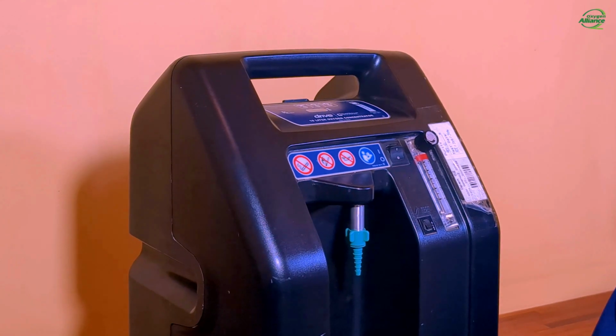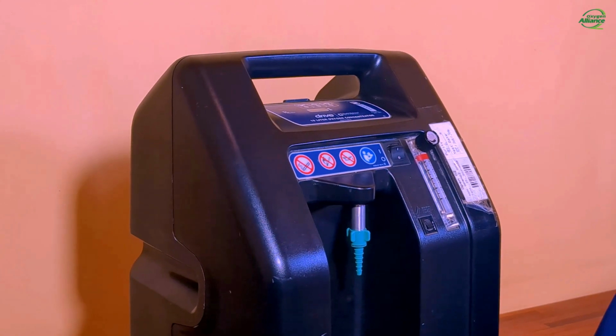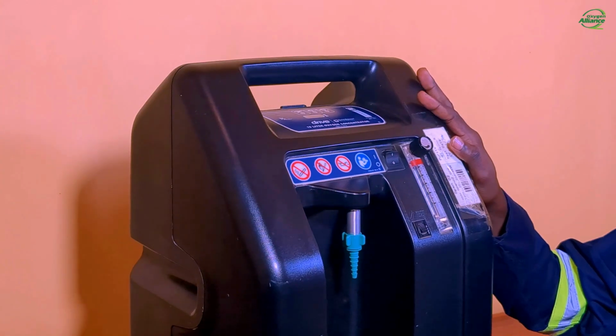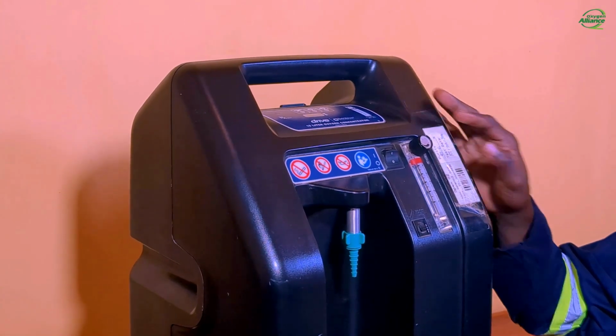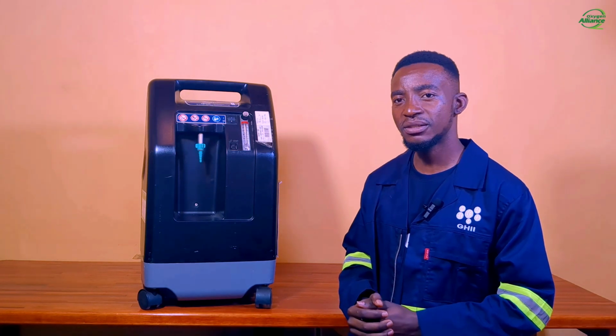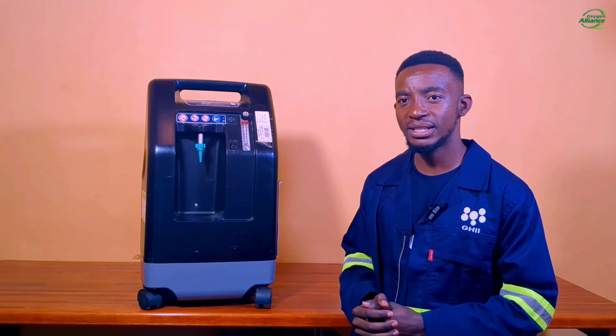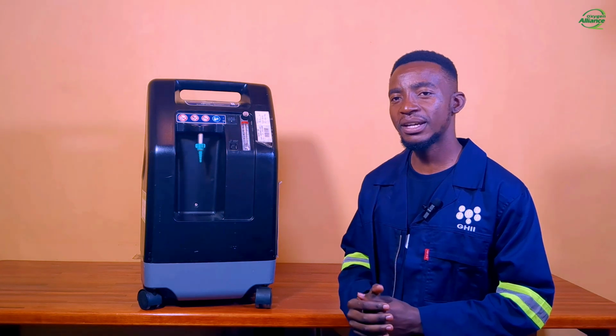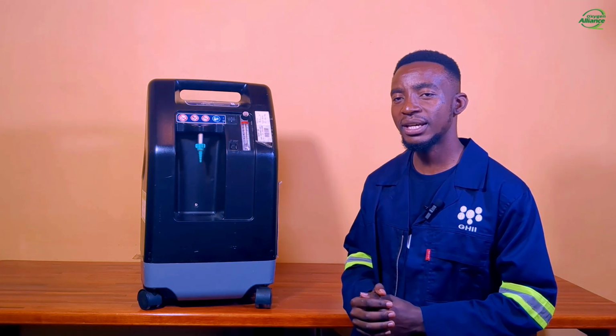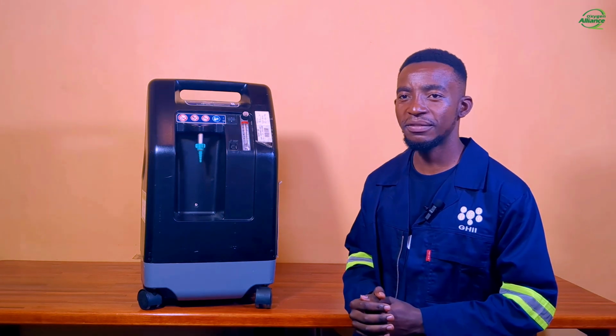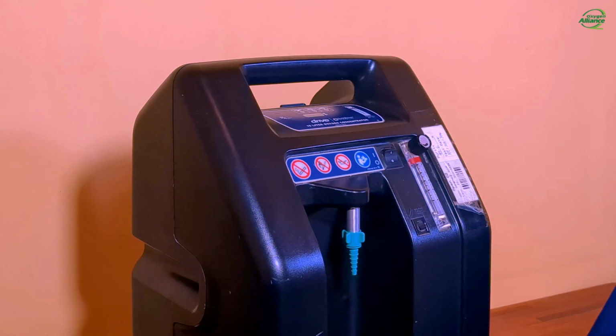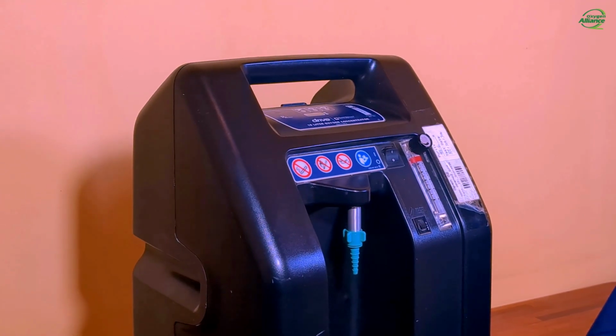The DeVilbiss 1025 Oxygen Concentrator has a maximum capacity of 10 liters per minute, and it delivers oxygen with a concentration from 87 to 95.6%. So this model, there are three variants of this model, the difference being the voltage rating. We have the 1025 DS, which is 110 volts AC, and we have the 1025 KS, which is 230 volts AC, and last we have the 1025 UK, which is 240 volts AC.